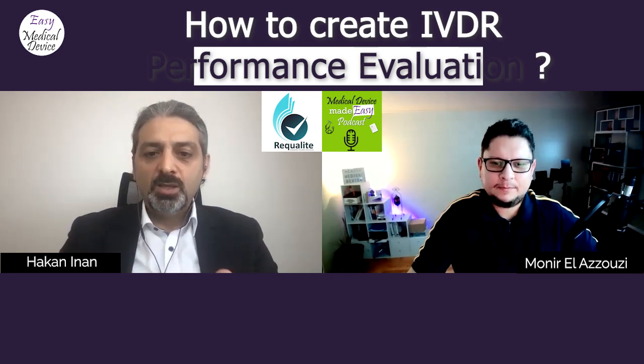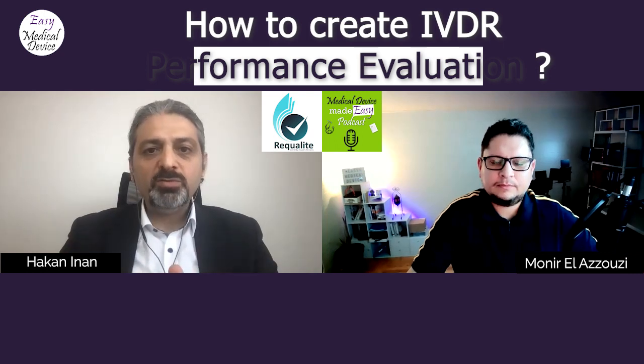Now, when you look at the regulation, it specifically describes 6 reports, Munir. 5 of them are reports, and 1 of them is a plan. Article 56 in the IVDR describes performance evaluation, scientific validity, analytical performance, clinical performance, what they are and how we need to do it. And then Annex 13, Part A, gives us the design information.